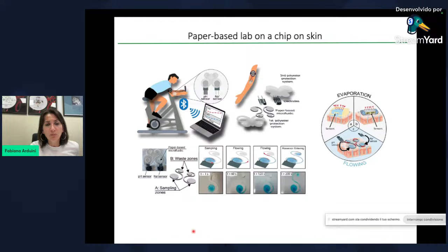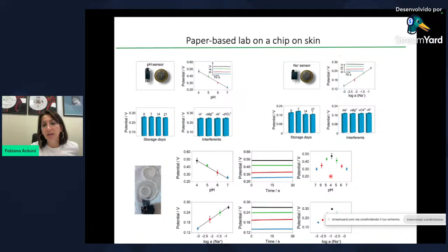And this is very important, that we studied the hysteresis, and we can see that starting from pH 7, moving to pH 4, and coming back to pH 7, you obtain the same results without memory effect. This demonstrates that it's possible to detect the pH, and also the sodium concentration, in continuous without memory effect. This is the continuous analysis, and we tested the sample only at the end by the reference method, obtaining good agreement. So with the reference method, we detect the amount of sodium, for example, only at the end.